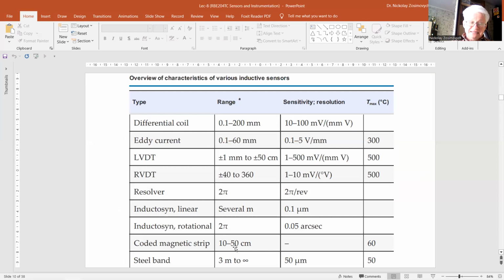The overview, this table at the end of this section lists some general characteristics of the LVDT. The rotational version of the LVDT is the RVDT, the rotational variable differential transformer. The principle of operation is the same as for the LVDT due to the particular configuration of the coil, and the range is restricted to less than 180-degree rotation.